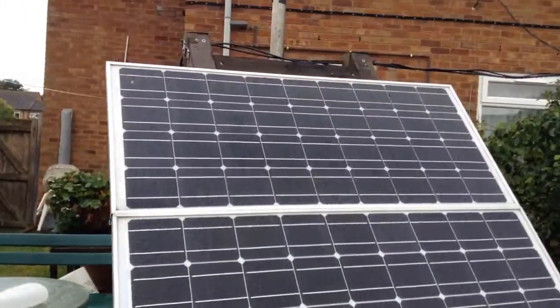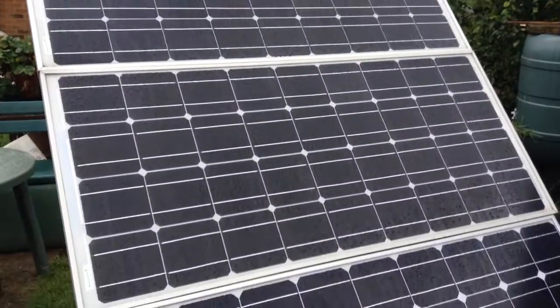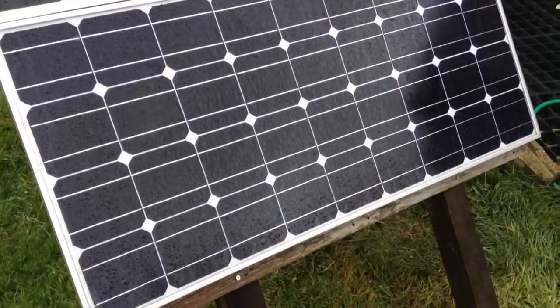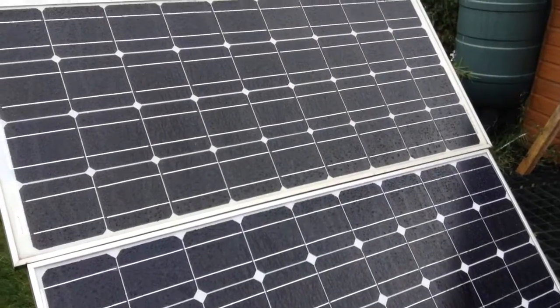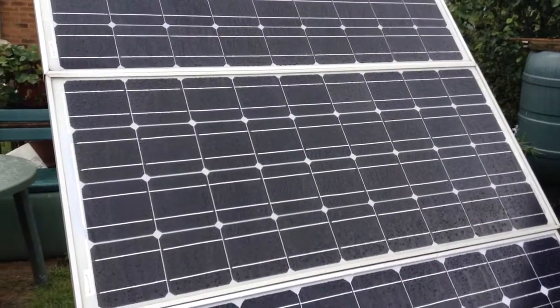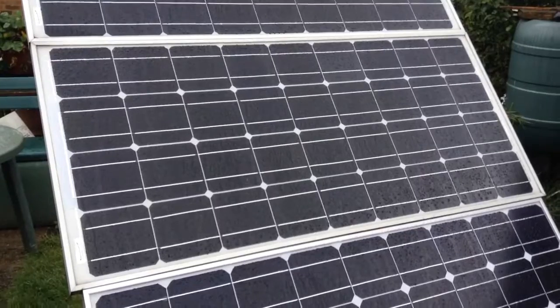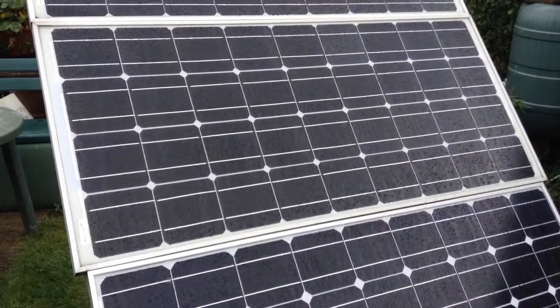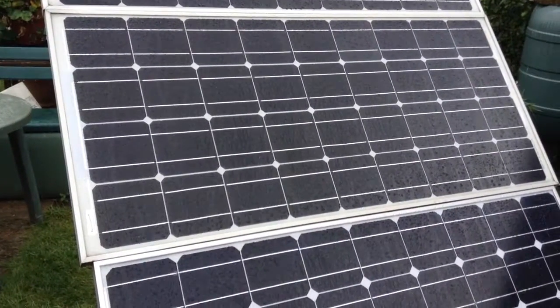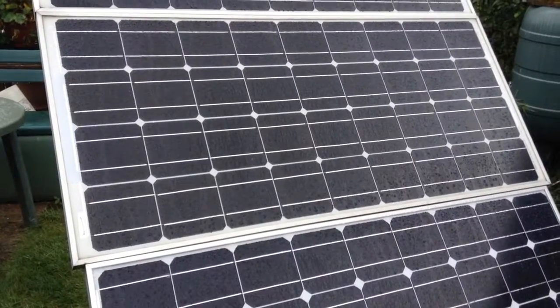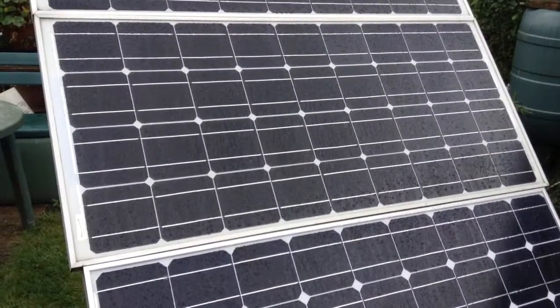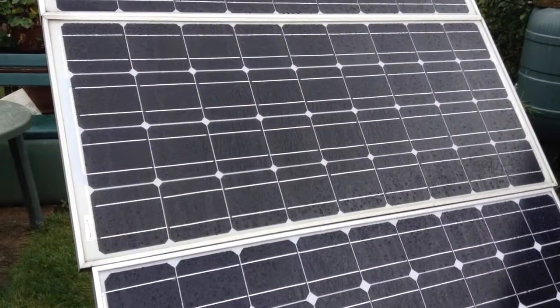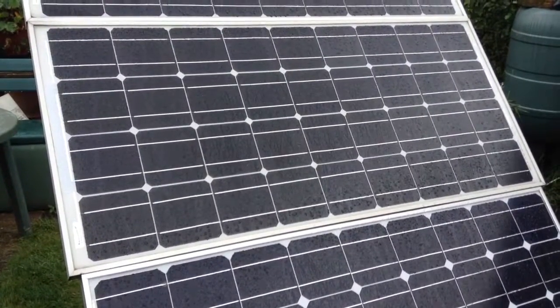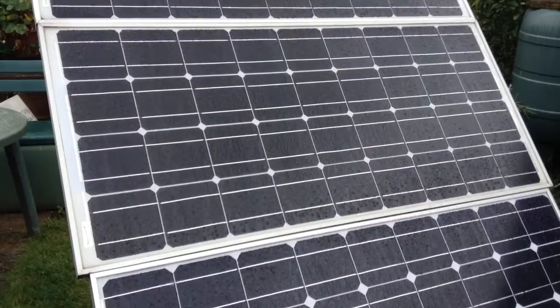I wire my panels in series because I am using an MPPT charge controller. That stands for Maximum Power Point Tracking, and basically it can convert the high voltage from the solar panels down to the correct voltage to charge the batteries. There are cheaper charge controllers on the market called PWM, that stands for Pulse Width Modulation, but they cannot convert the high voltage down to the voltage of the batteries.